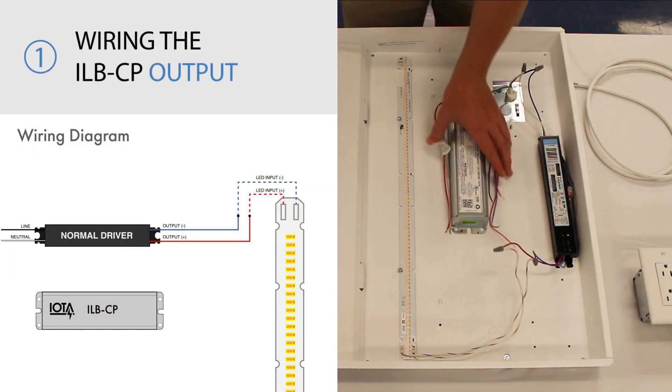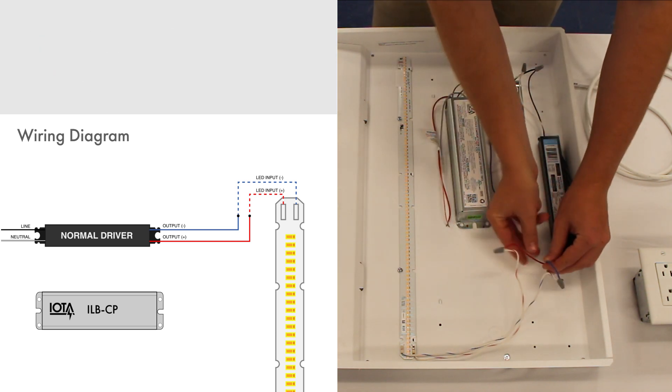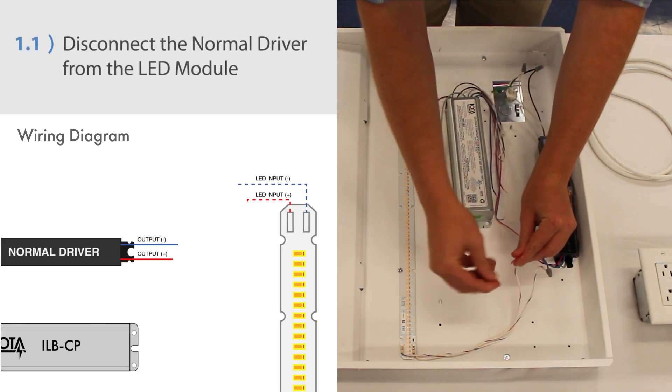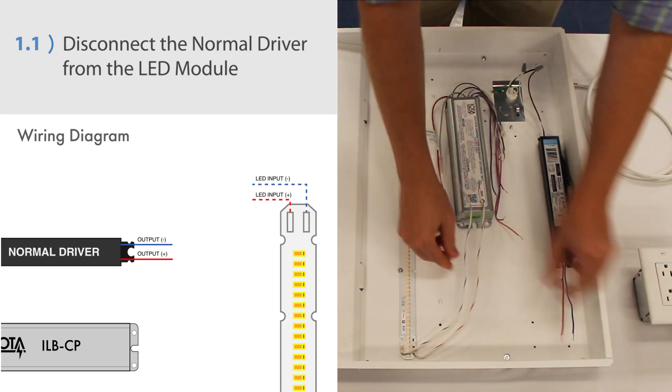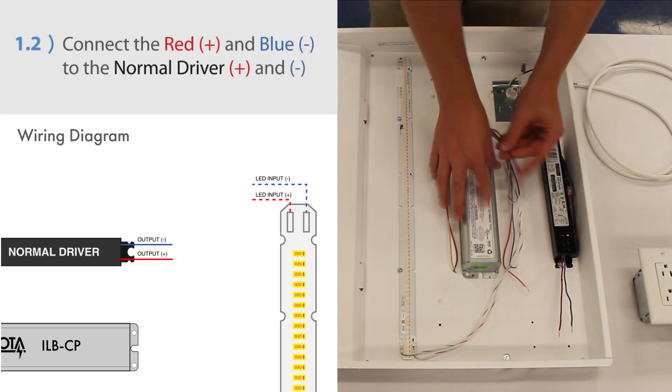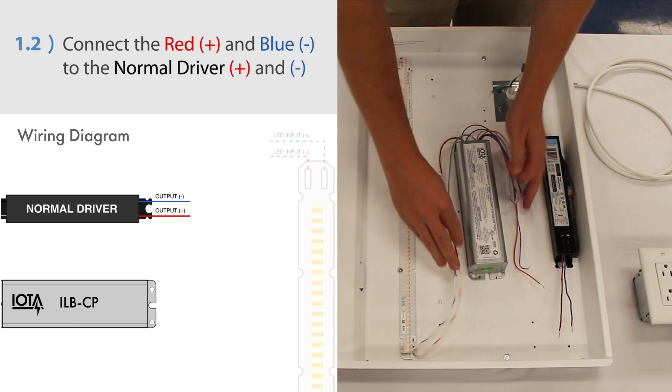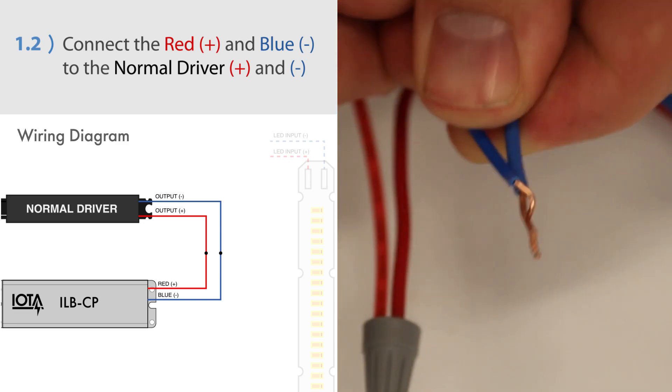The first step will be to wire the output. First, disconnect the leads connecting the normal driver to the LED module. Then, connect the red positive and blue negative wires from the ILB-CP to the positive and negative output wires of the normal driver. Be sure to observe polarity.